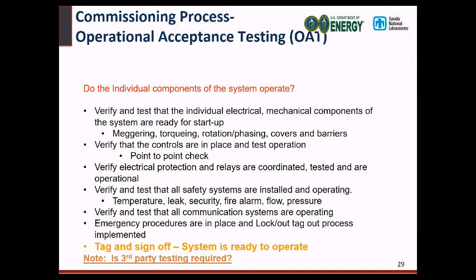So we'll go into a little bit of the operational acceptance testing. Here we're just starting up the system, making sure everything works at your site. They do meggering to make sure there are no shorts, you're torquing down the wires, making sure they're torqued to the right pounds. You're looking at the rotation and phasing so you don't have an A phase going to a B phase. And also the covers and barriers. When you have exposed energized parts, you want to make sure they are covered. The barriers are not just for panels and the system itself, but you might actually have a gate that needs to be put in place.